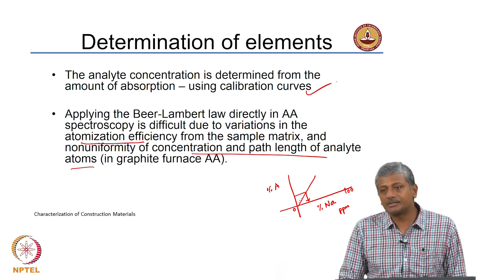Our points will be only somewhere here, and then you prepare a calibration curve, which is nothing but a regression line through the points, so that for whatever absorption level you get, you can read out the specific percentage of sodium that you have in your sample. That is a calibration curve. You are producing known samples, just like what you do with the chloride electrode in the lab. We prepare chloride solutions with different concentrations of the chloride ions, and then use the electrode to determine what the voltage is for specific concentrations of chlorides in your solution. Similarly, we prepare a calibration curve in this case. So, that is how you will determine the concentration of the analyte inside the gaseous system.